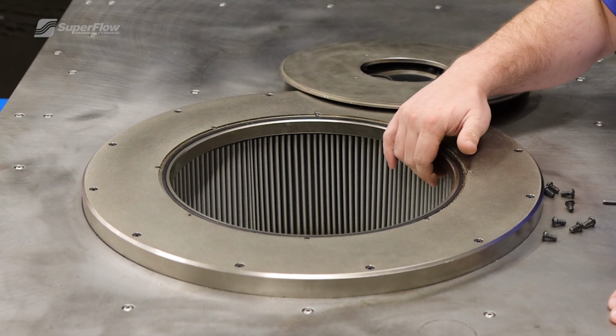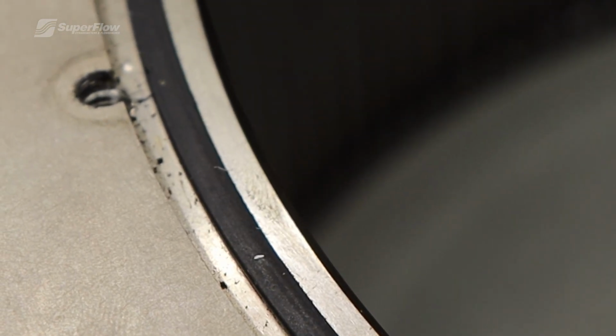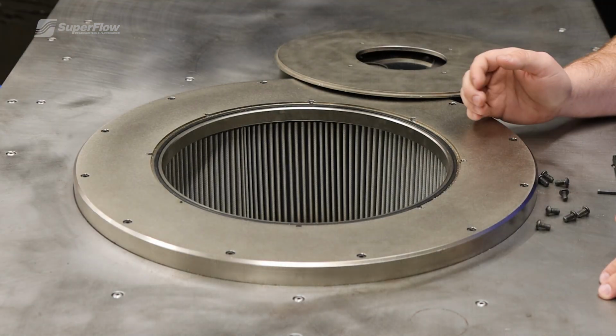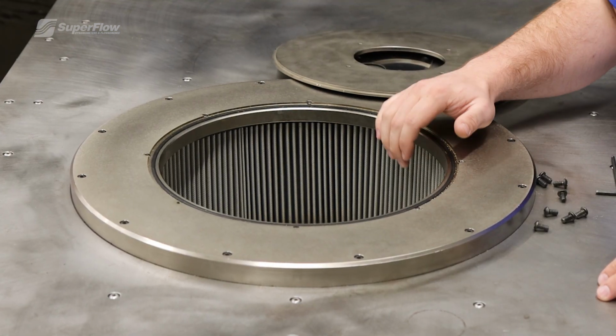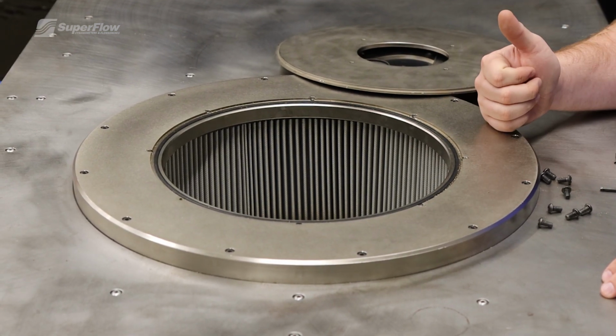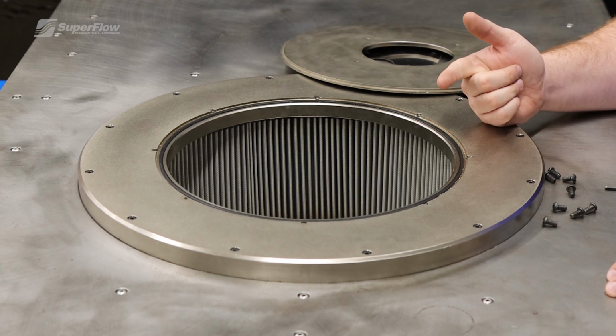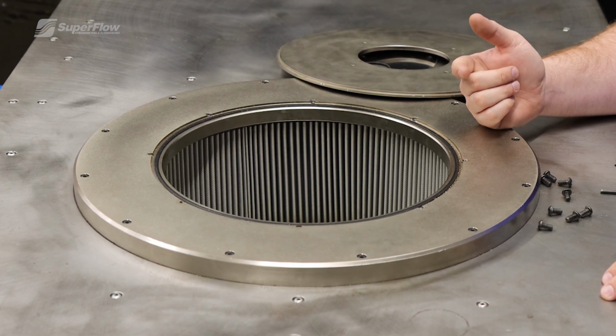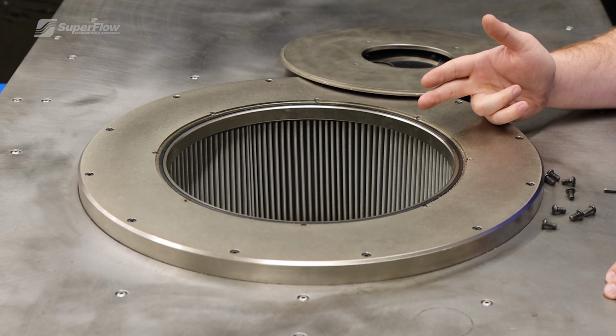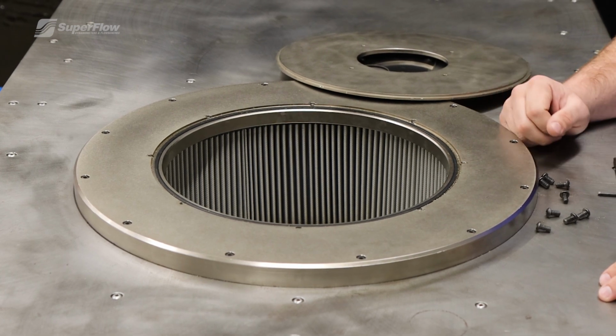Beneath that is your filter assembly. This can also cause misreadings in your calibration or your test fixtures. We recommend replacing the filter once a year, or if you get any misreadings, or before any calibration is performed.